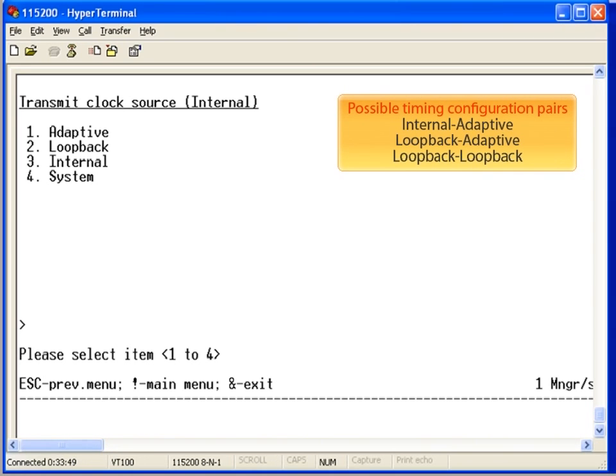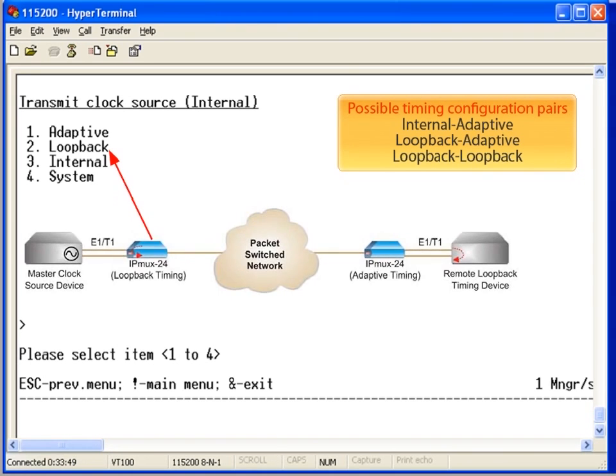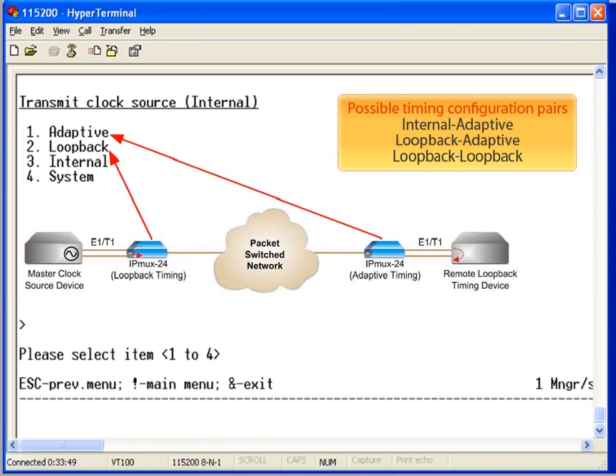There are four possible configuration options for the T1 clock: Adaptive, loopback, internal, or system. When set for internal clock, the IPMUX generates the T1 clock.